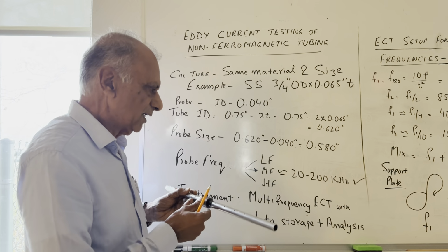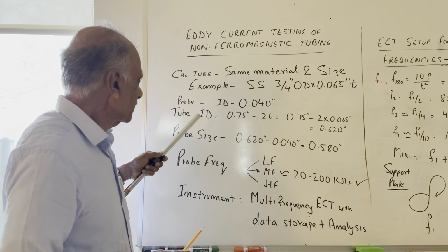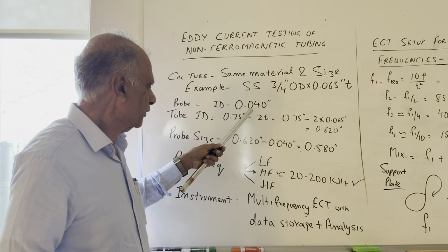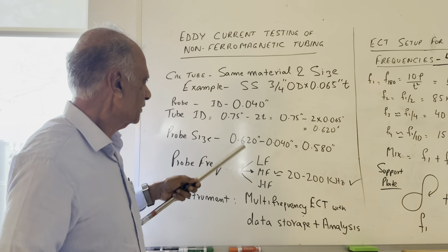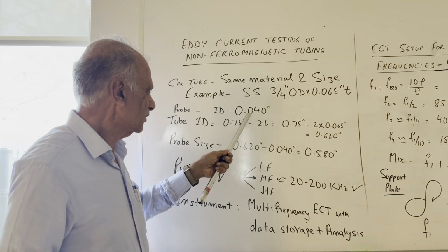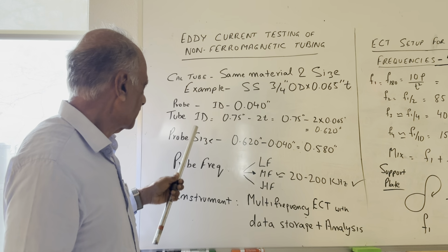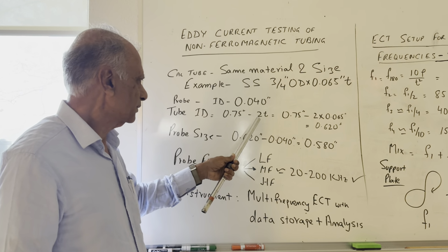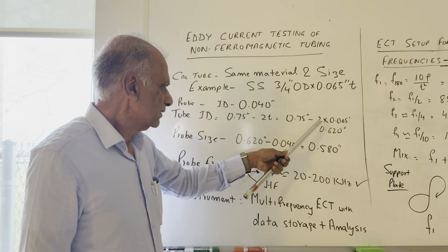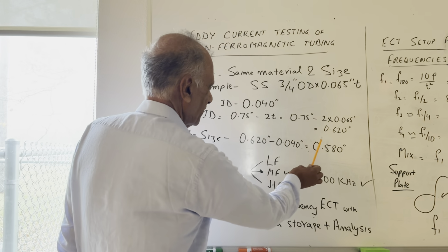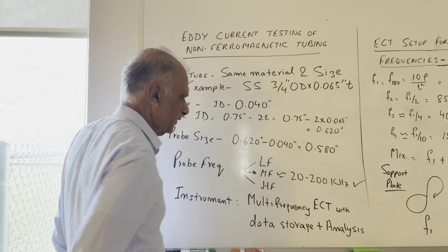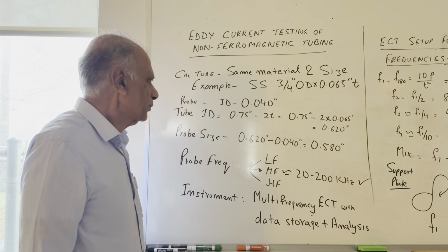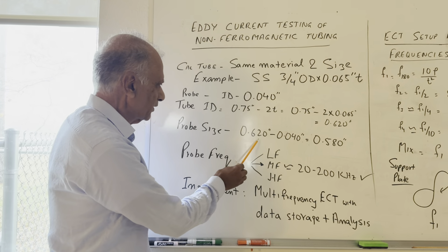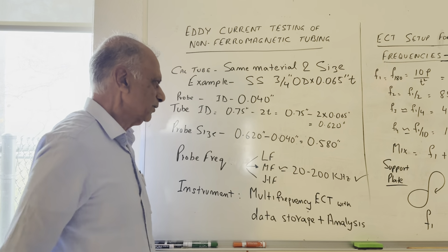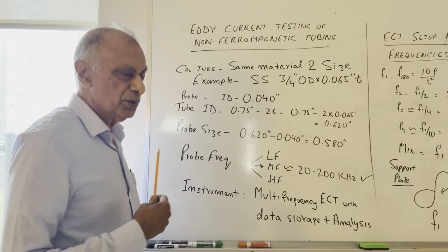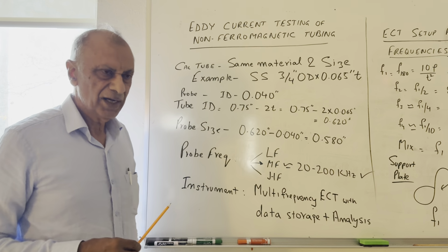Now when we start with this inspection, we have to select the probe. The probe has to be 0.04 inch less than the ID of the tube. So whatever the ID is, not the OD, ID minus 0.040. In this case, the ID is OD minus 2T, that's 0.75 inch minus 2 times 0.065 inch, and the ID of this tube is 0.620 inch. Based on that ID, the probe size will be 0.620 inch minus 0.040 inch, which comes out to be 0.580. So you would need a bobbin probe with the size of 580.